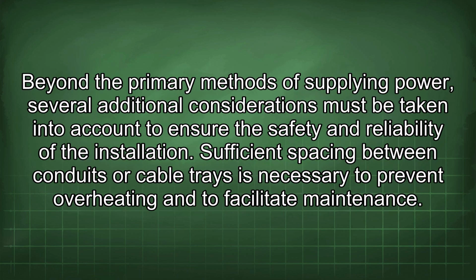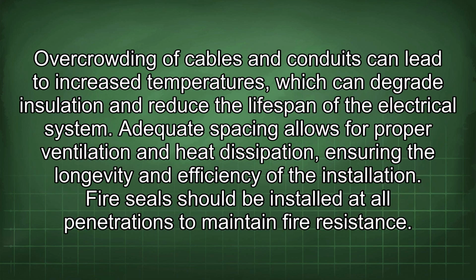Beyond the primary methods of supplying power, several additional considerations must be taken into account to ensure the safety and reliability of the installation. Sufficient spacing between conduits or cable trays is necessary to prevent overheating and to facilitate maintenance. Overcrowding of cables and conduits can lead to increased temperatures, which can degrade insulation and reduce the lifespan of the electrical system. Adequate spacing allows for proper ventilation and heat dissipation, ensuring the longevity and efficiency of the installation.